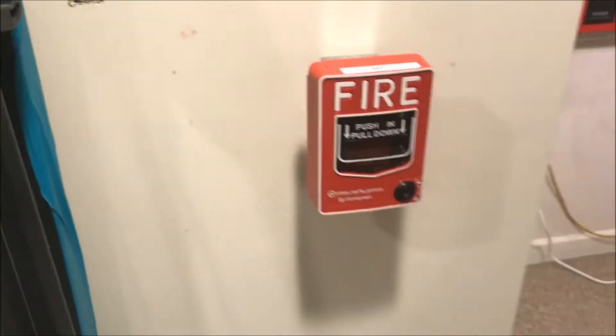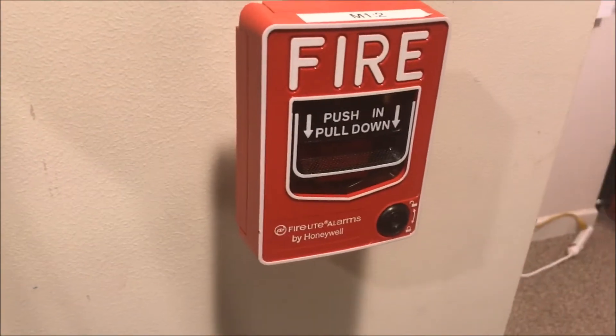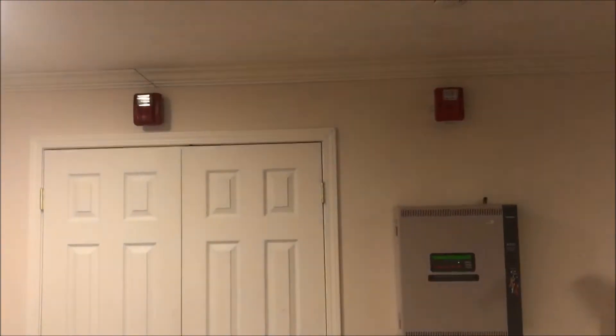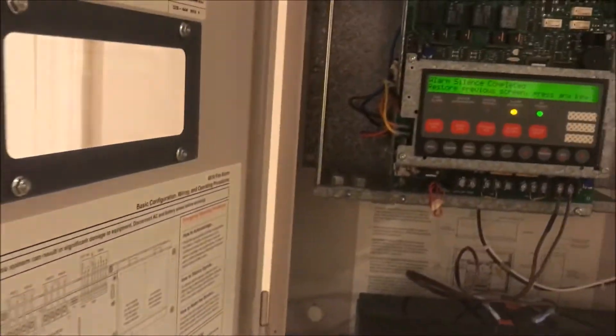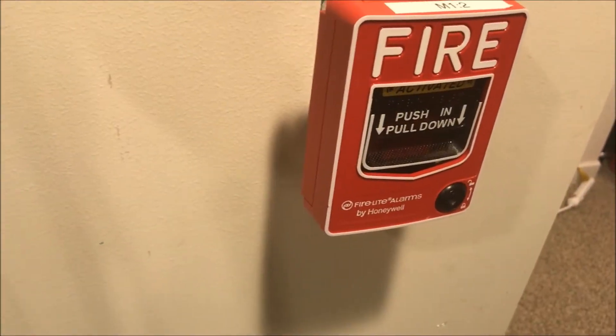We hit exit so we get a system normal. It's a mess down here so we're just going to pretend like you don't see it. It's 61 degrees in February in Cleveland - what the heck is going on? It's too warm, we've got to evacuate the building. I got that extra B key, let's reset the pull station so you can see - you pulled it, there's your alarm going off. This test is getting long already at nine minutes.